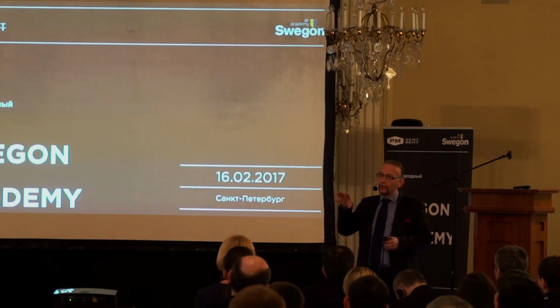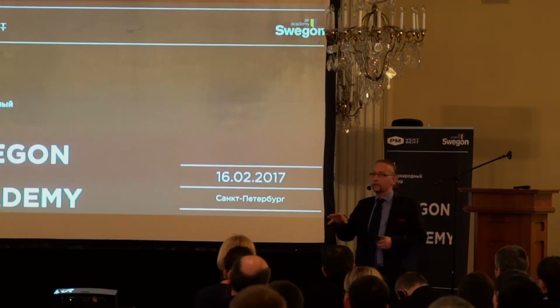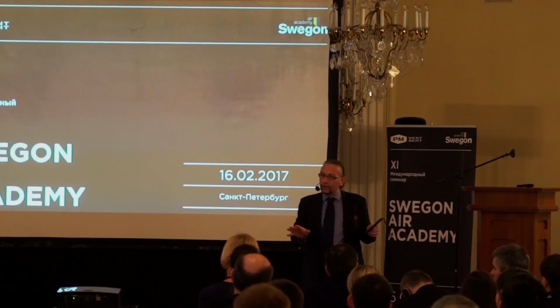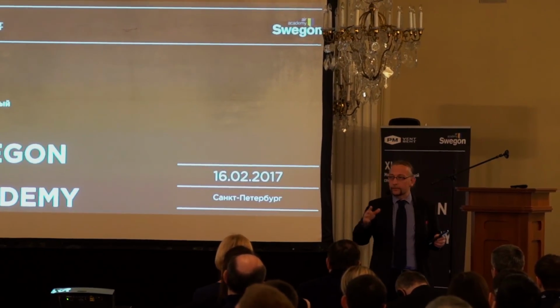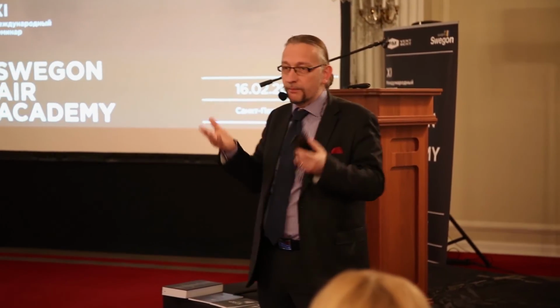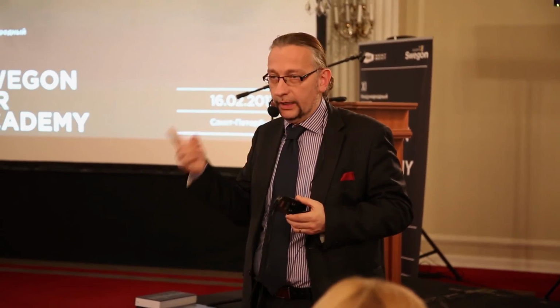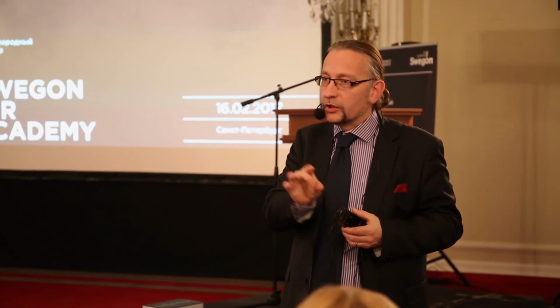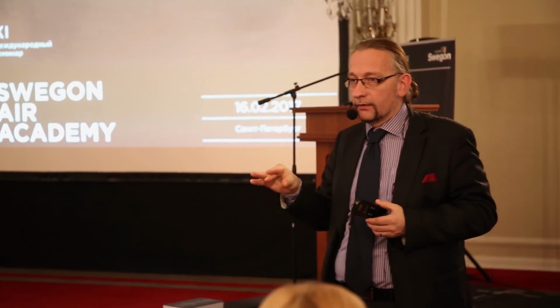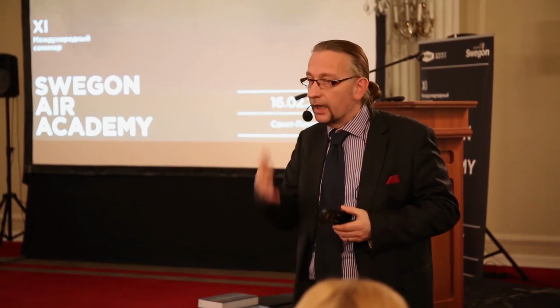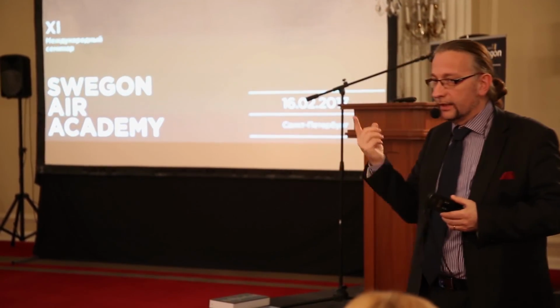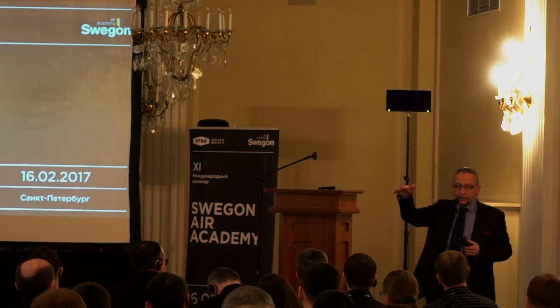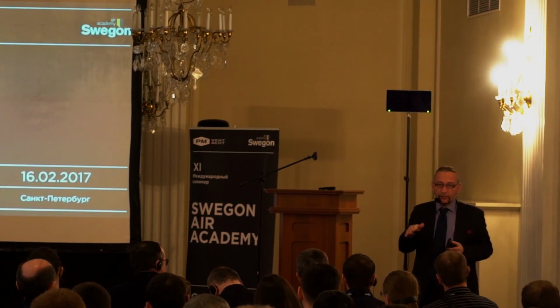And then it's always extract from the bathroom, always supply into the bedroom. And then it's transfer air between the bedroom and the bathroom. It's standard, okay? But it has to be always in balance, more or less. And it has to be, as you say correctly, ventilated all day, all night. And always from the bathroom, but much less. So one saving when nobody's in the hotel room would be to bring down the air volume. The standard hotel system, however, will have 80 cubic meters per hour constant all the time. That is the standard all over the world nowadays. But today, the idea is to save energy by reducing to 40 cubic meters, so about half.